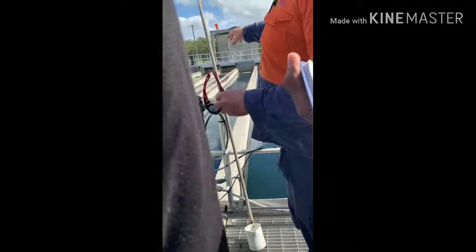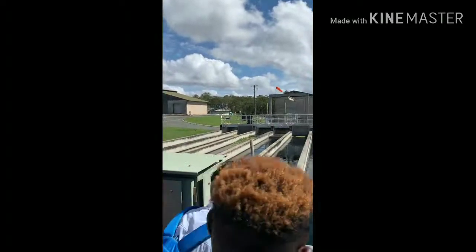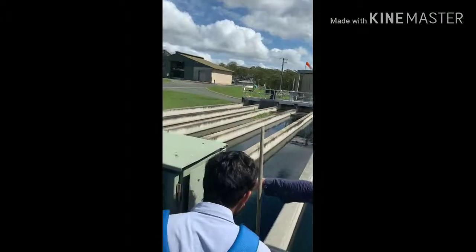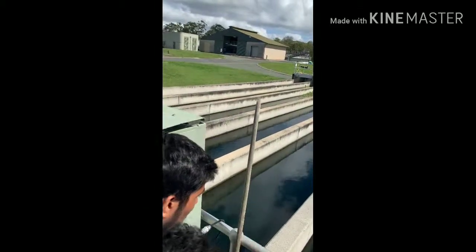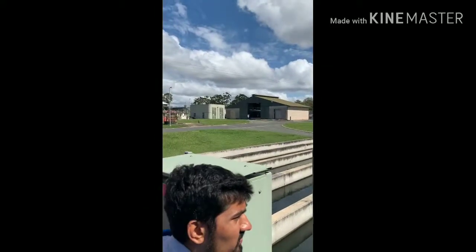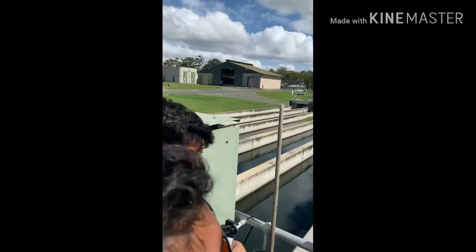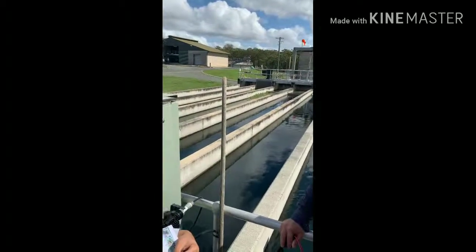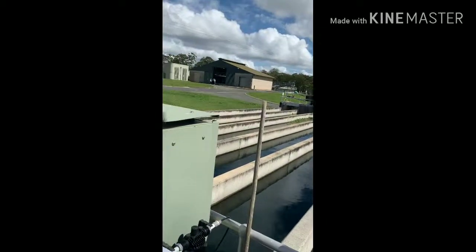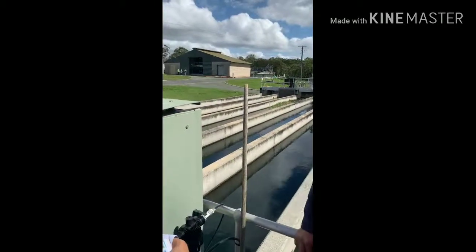Okay, so we've got, this is side one, so that back to there, one over there, one here, this is all side one, and this all goes to Whipping Creek, straight into the river system. That's why we dechlorinate, so we dose SBS, sodium bisulfite solution, which will kill off the chlorine, so there's basically no chlorine residual going into the river systems.